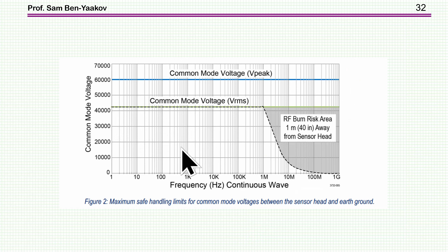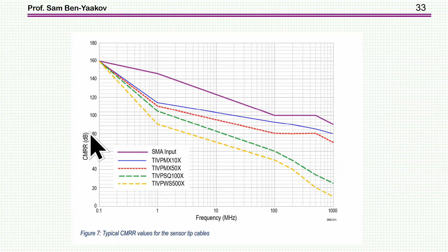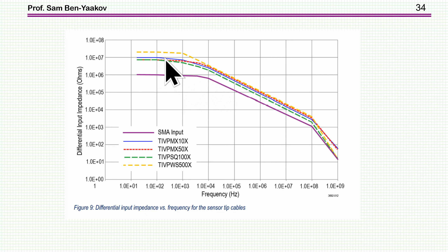And here now we see the common mode rejection ratio for the various tips, various amplifiers, starting at 160 and of course going down to lower values. This is not a plus sign, not a minus sign, so it's going down. And here is now the input impedance. Again, nothing special about it, because the amplifier is an amplifier. I mean, there's nothing new about that. So it has the characteristics of an amplifier except for the common mode rejection ratio, because the amplifier has no connection to ground whatsoever. All the power is coming through the fiber optics. So only the very minute capacitances are affecting some leakage to the ground. And we see here again the drop in the impedance.